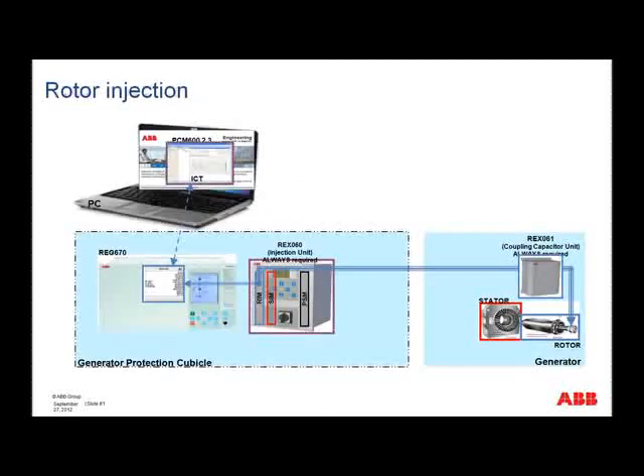And here we have the injection principle. Once again, you would need the injection unit. But now instead of using the injection for the stator, we would use the injection for the rotor, and we would connect this to the rotor, and feed the quantities to the IED, so the IED would be able to interpret the injected quantities and decide whether the rotor had an earth fault or not.